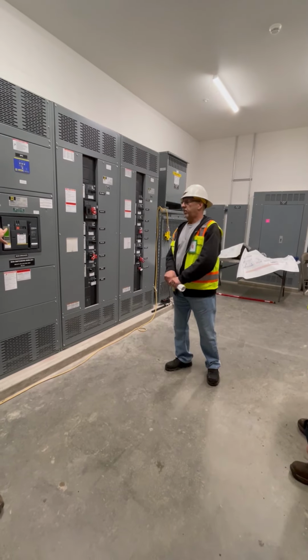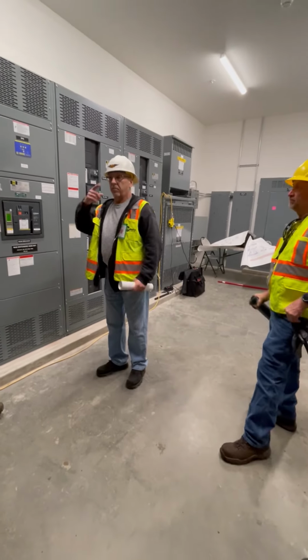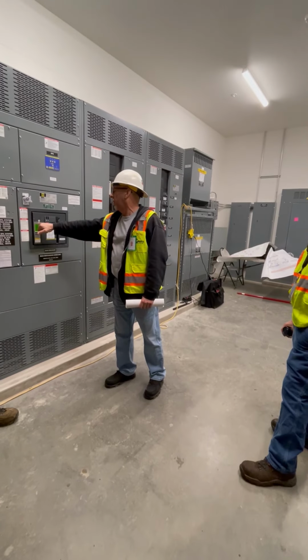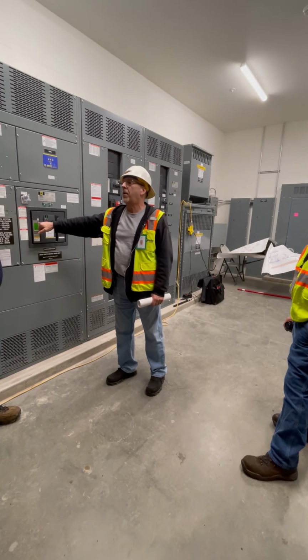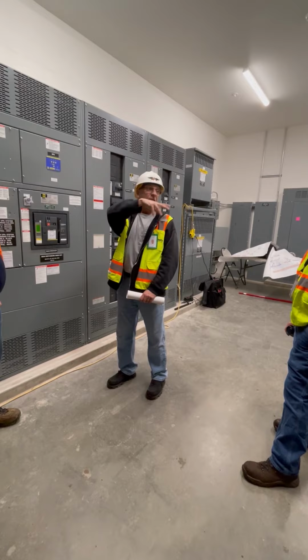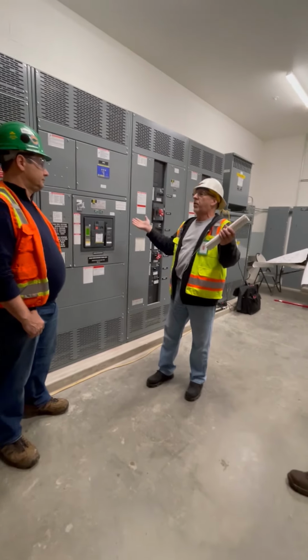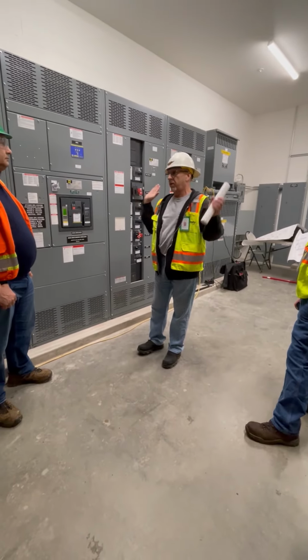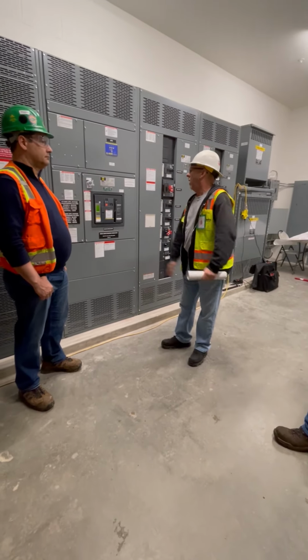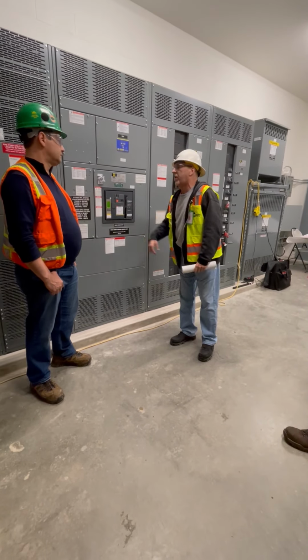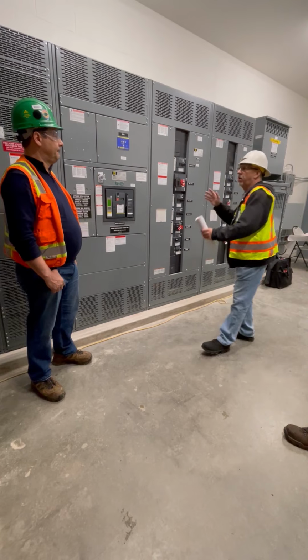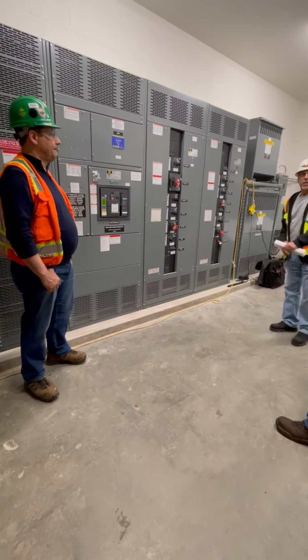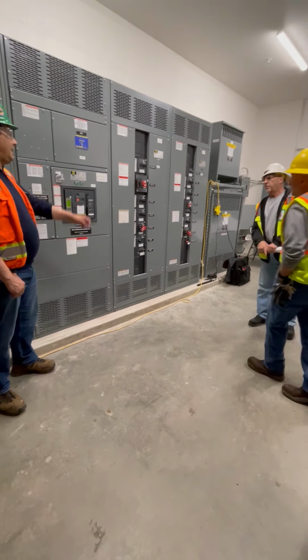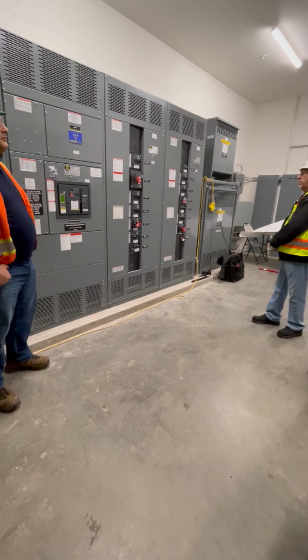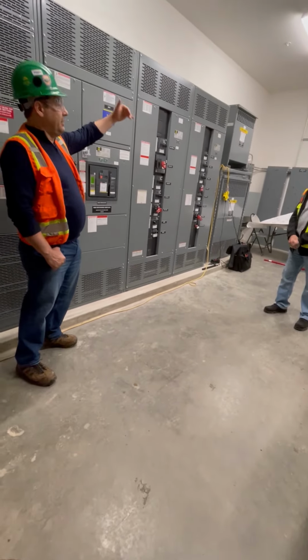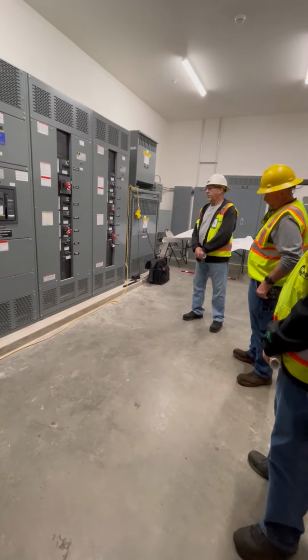Again, these LEDs are good, because like you said, they'll tell you ground fault, so then you know how to proceed from there instead of guessing. When it happened at Fisher's Landing, we had no idea why the breaker was tripping, and troubleshooting was phenomenally a pain in the butt. There's no generator there. Here you get ground fault, and then you can say, okay, start doing it this way. It's very handy to have that. And then you can use the wall lines for process of elimination to see what's on that feeder and start going downstream to figure it out, right?